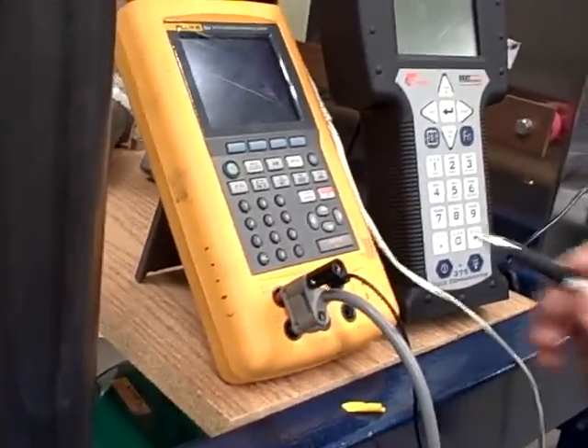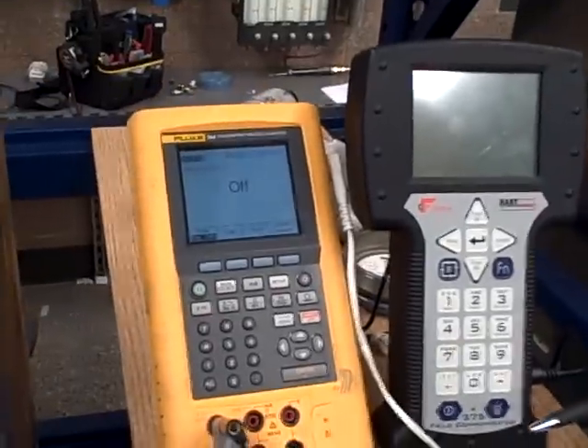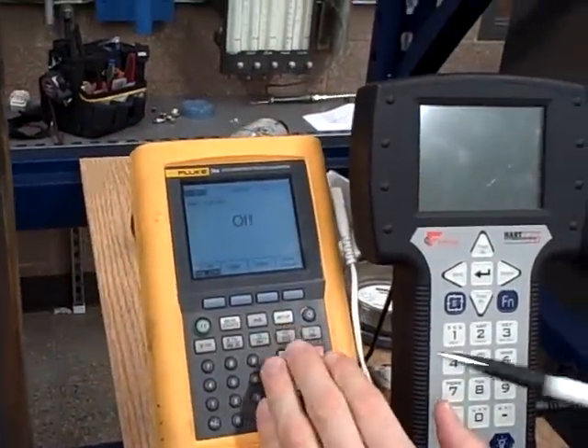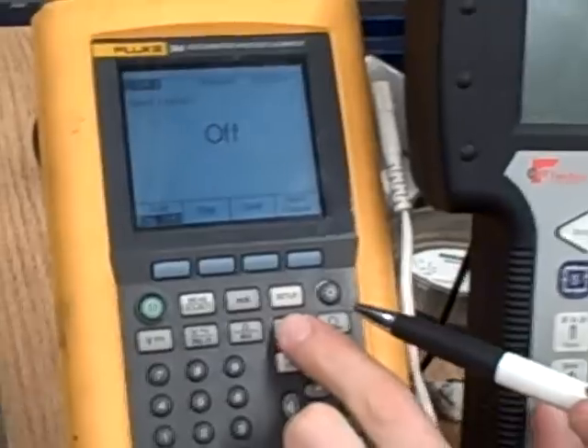Next, we set up the Fluke 744 to be a source of resistance to simulate an RTD. First we hit the Measure Source button until Source appears on the screen. Then we tell it what to source. I want to go for RTD, so I hit the TC RTD button.